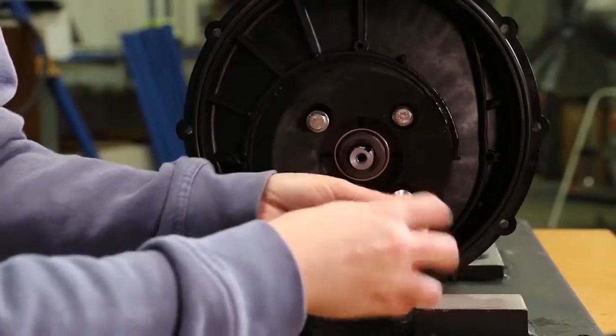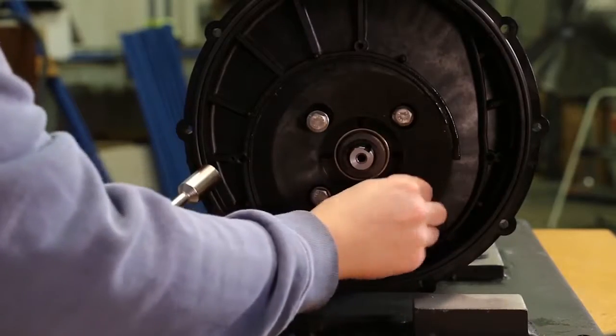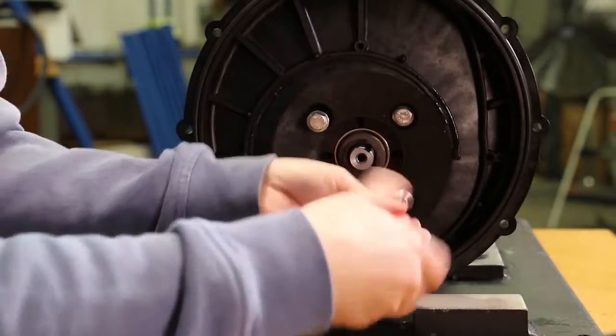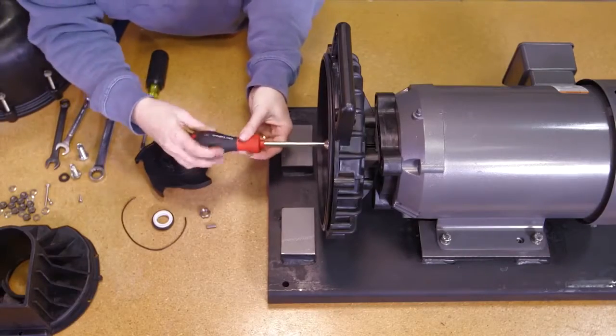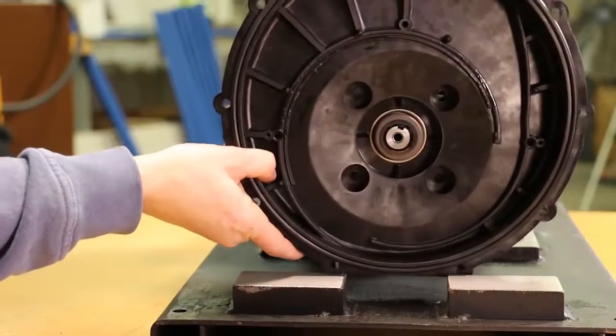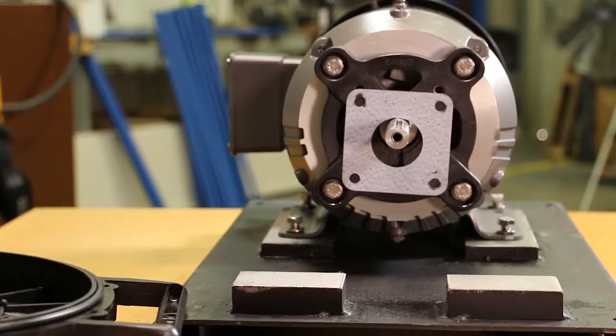Remove the four rear bracket screws, rear bracket washers, and screw head O-rings from the rear bracket using a half-inch socket. With the four rear bracket screws removed, the rear bracket can now be removed from the drive unit.